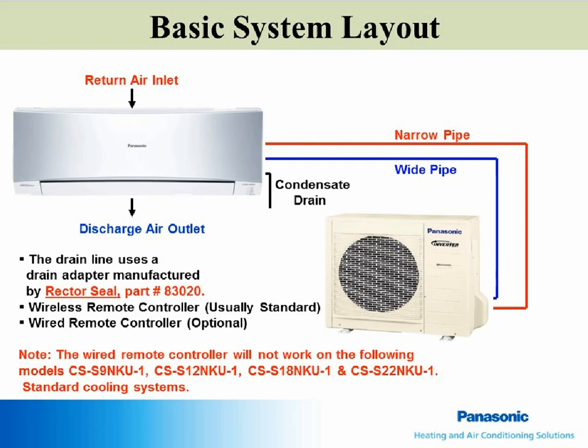Shown is the basic system layout for a wall-mounted single-zone mini-split. Other styles and multi-zone models are very similar. Two separately insulated refrigerant lines connect each indoor unit to the outdoor unit. Each indoor unit has a condensate drain, and a PVC adapter is included that will allow this drain to connect to a 3/4" PVC pipe.